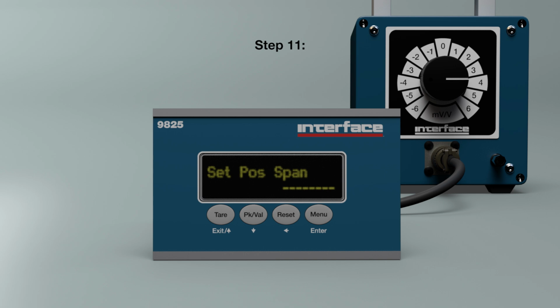Step 11. Once the 9825 has finished recording the C1 value, C2 will be displayed. For this example, we will only be using one cal point on the positive span. Leave the C2 value set to 000000 and press the menu key to exit. The Set Positive Span menu item will be displayed.